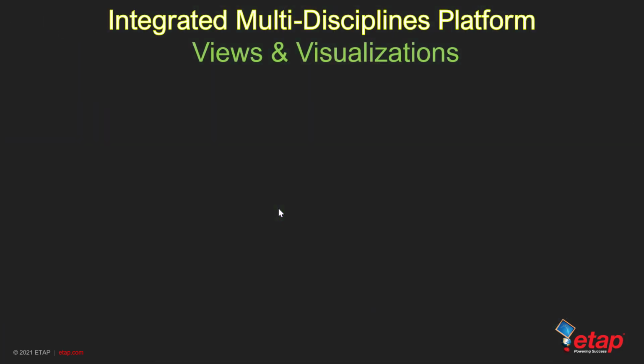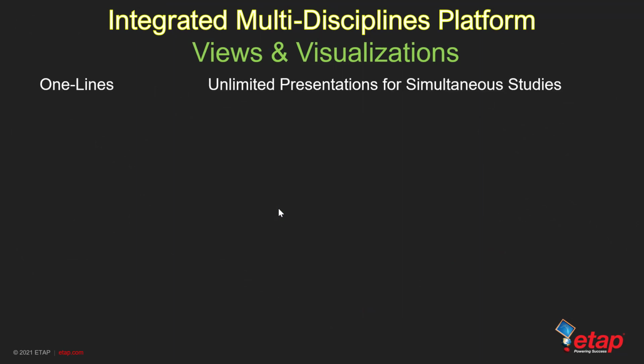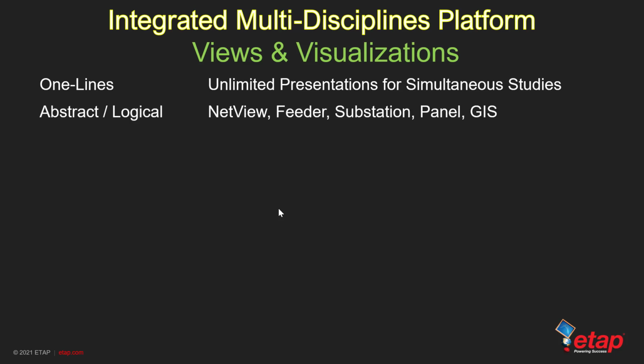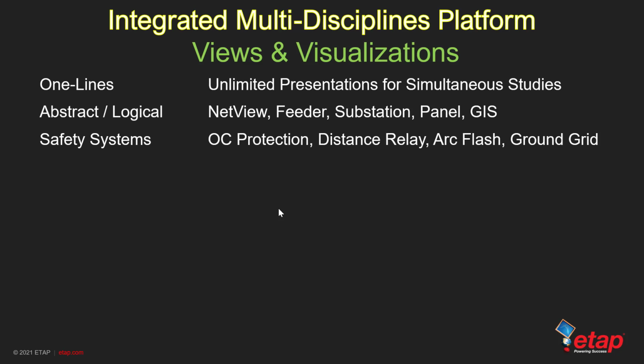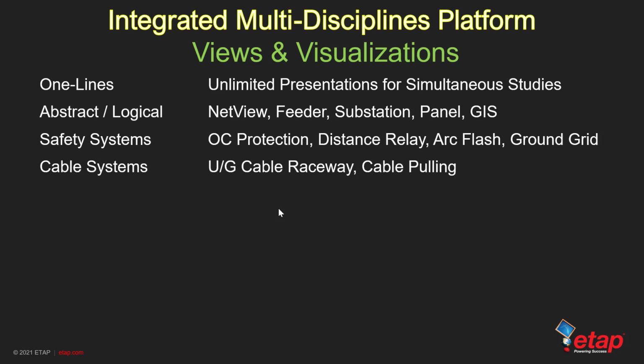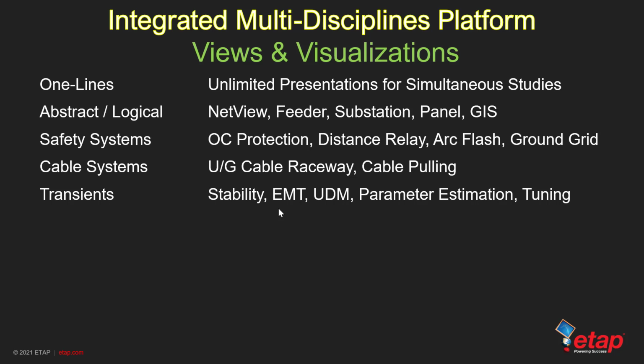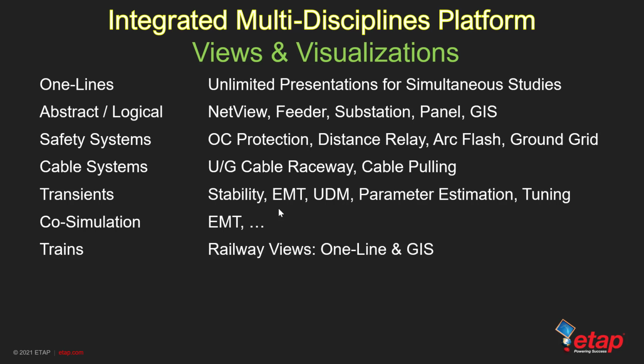So what are the other niceties of this platform besides these multiple dimensions? The main thing is, of course, the one-line diagram, which allows unlimited presentations for simultaneous studies. You have abstract and logical views like network view, feeder view, substation view, panels, GIS, safety systems, overcurrent protection, distance relays, arc flash, ground grid, underground cable raceways and cable pulling, stability analysis, electromagnetic transient analysis, user-defined dynamic models, parameter estimation, parameter tuning, and co-simulation with EMTP, Simulink and other tools for transient analysis.